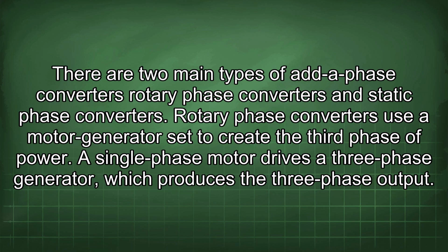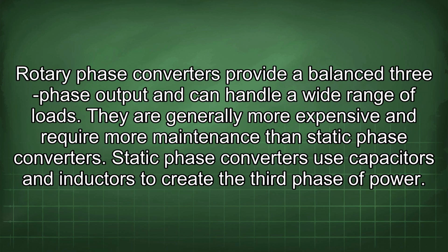Rotary phase converters use a motor generator set to create the third phase of power. A single-phase motor drives a three-phase generator, which produces the three-phase output. Rotary phase converters provide a balanced three-phase output and can handle a wide range of loads. They are generally more expensive and require more maintenance than static phase converters.